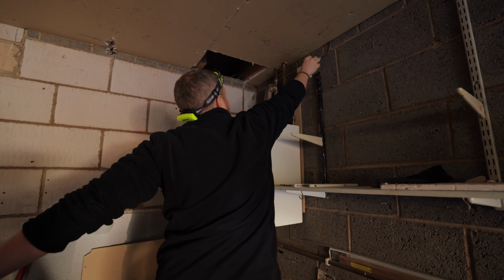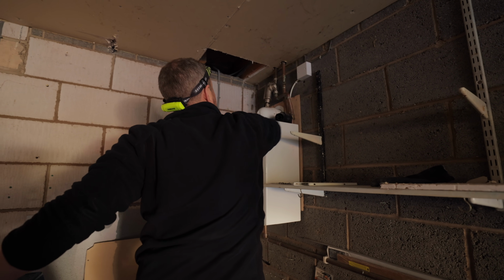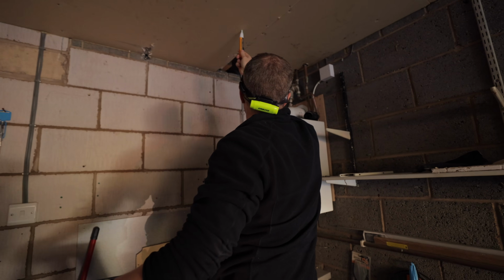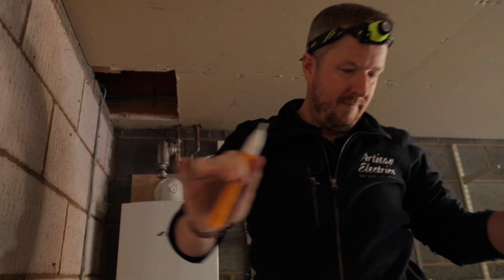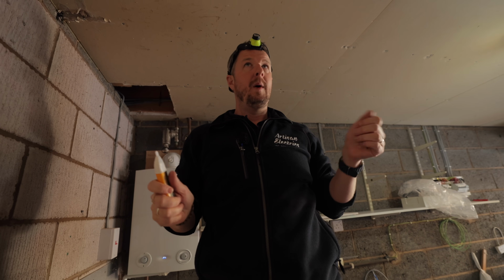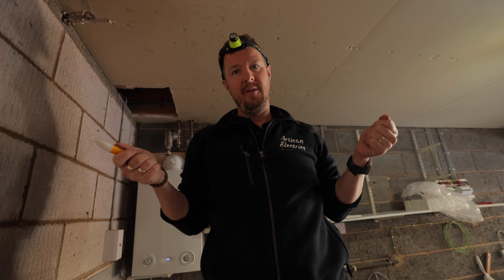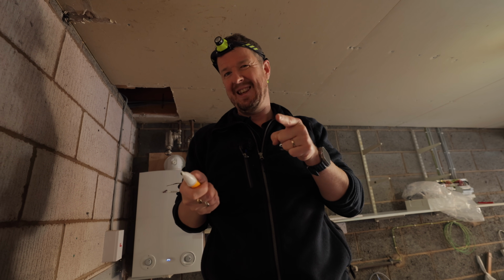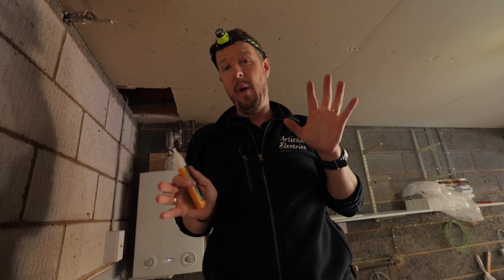Okay, still on. So actually the boiler is not on this circuit, so that eliminates that. So weird. Right, let's go back to basics here. We're testing to earth, but there's no voltage. But what if the earth is disconnected, or there's some kind of fault on the mains?